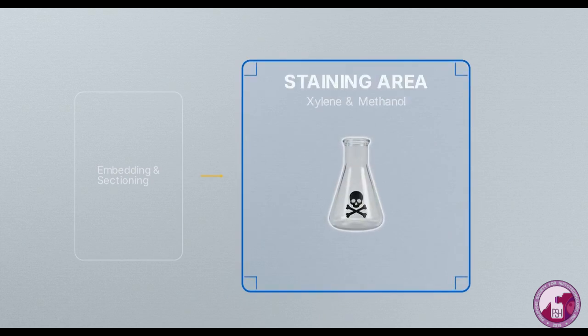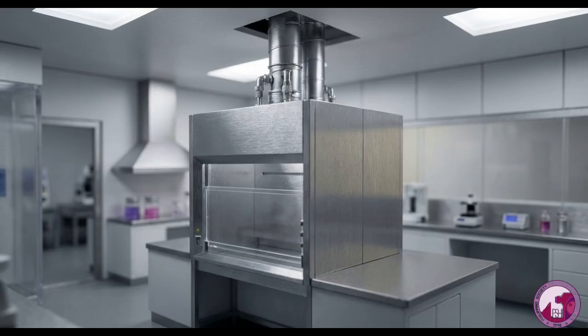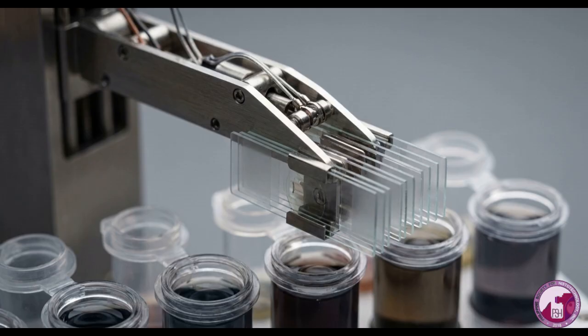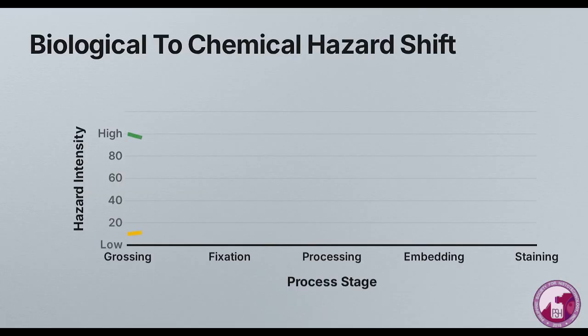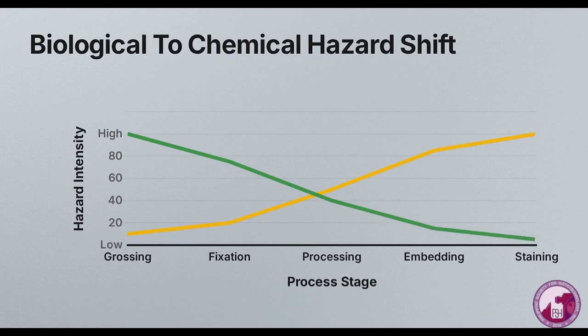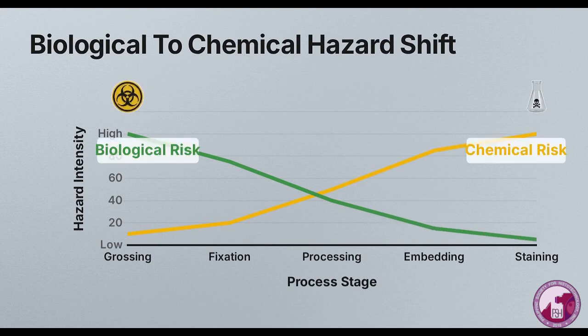Technicians use xylene and methanol to stain the cellular structures. Unlike the grossing zone, this area requires specialized fume hoods and uniquely targeted ventilation specifically engineered to handle volatile organics. Automated staining equipment is integrated here to handle these specific chemicals safely and consistently, minimizing direct human exposure. As the biological risk of the tissue decreases, the chemical risk to the staff peaks, requiring distinct, customized architectural segregation.